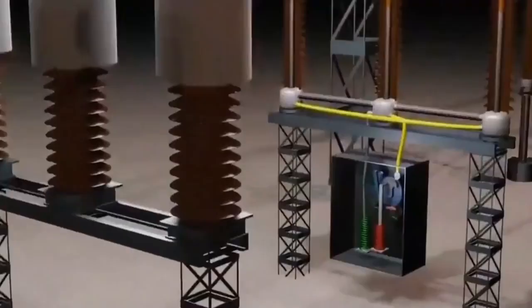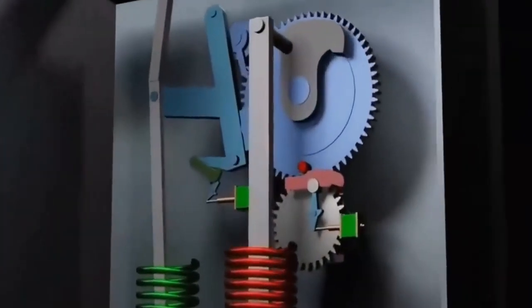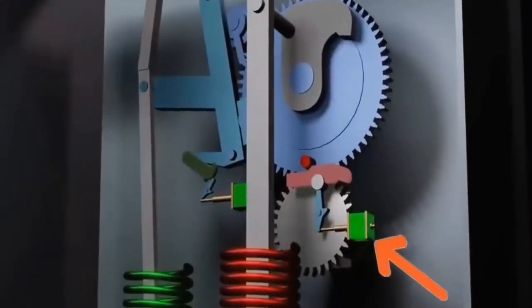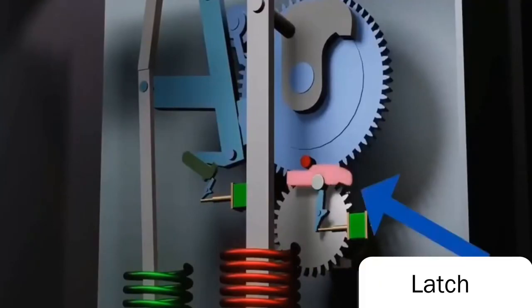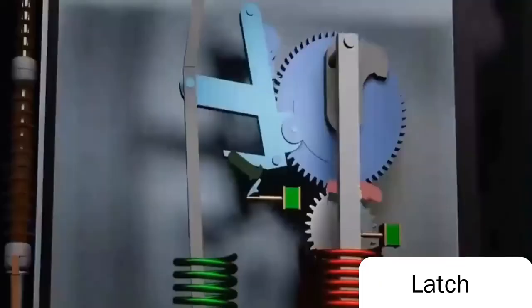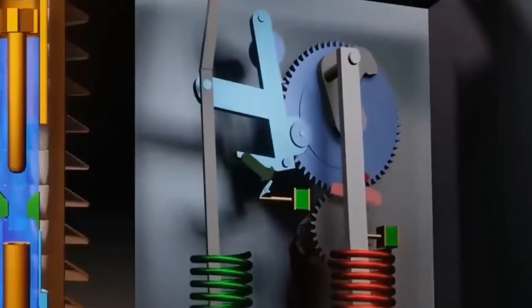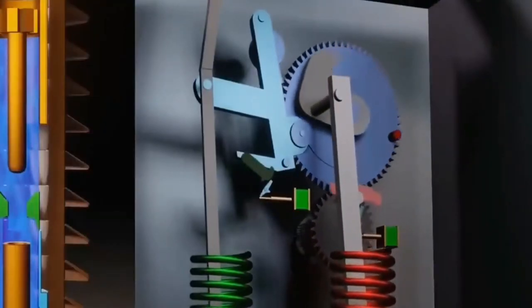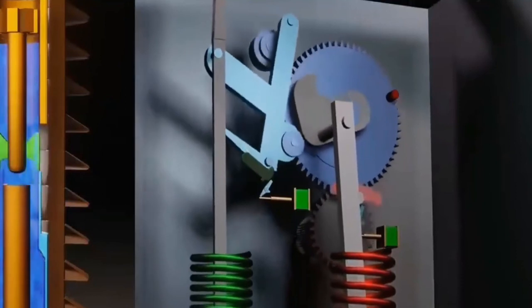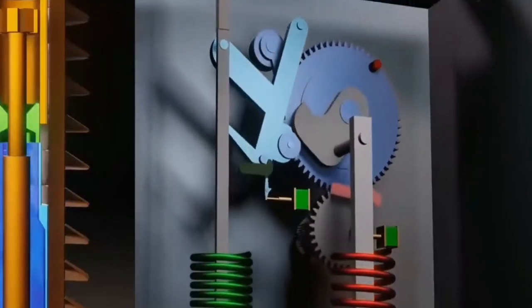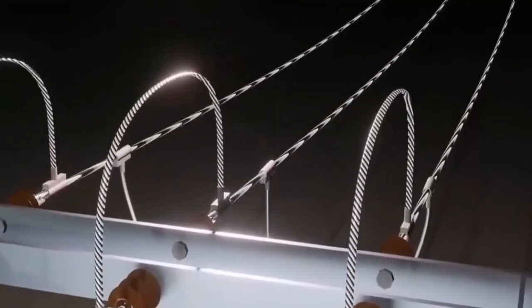Let's go back to the circuit breaker. In fact, there is also a relay on the right side here, with a mechanical design identical to the one on the left. When the relay receives a signal from the control panel, the plunger of the relay triggers the latch, which, when released, under the action of the spring, will start the rotation of the gear above, pulling up the lever on the left and compressing the spring on the left. This causes the piston of the circuit breaker to move up, connecting the entire transmission line.